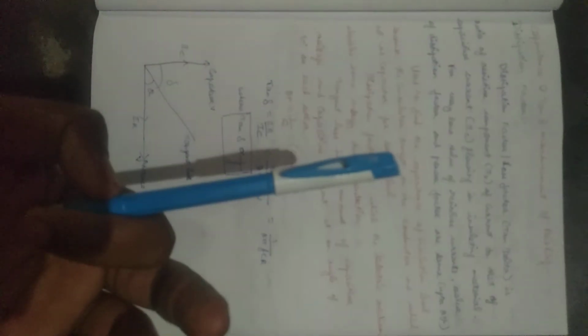Then this is your commonly known dissipation factor, tangent loss, which generally comes into your capacitance and tan delta measurement for any bushings or transformer windings, CVTs or current transformers, everything. And this also includes insulators. This is our common test which is carried out to check the healthiness of our insulator.